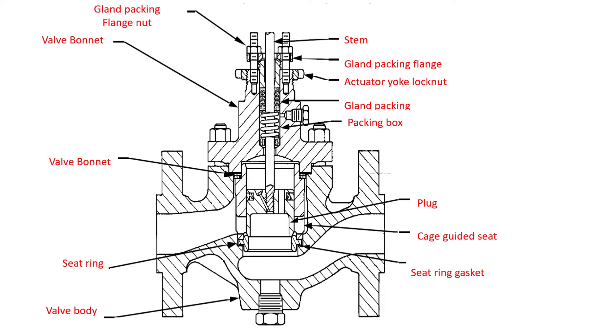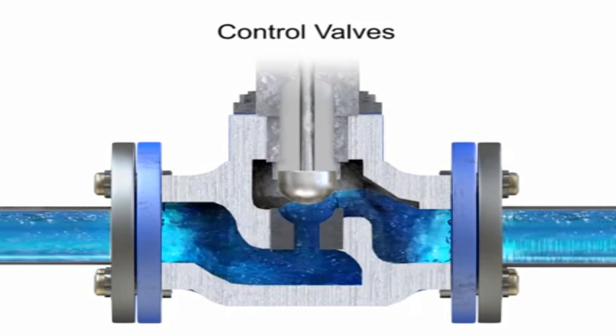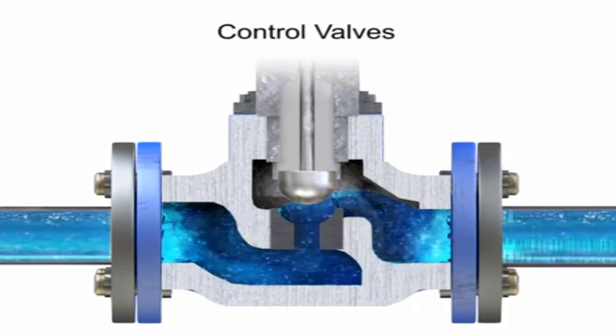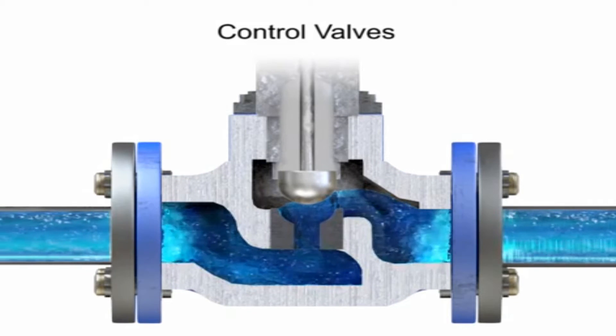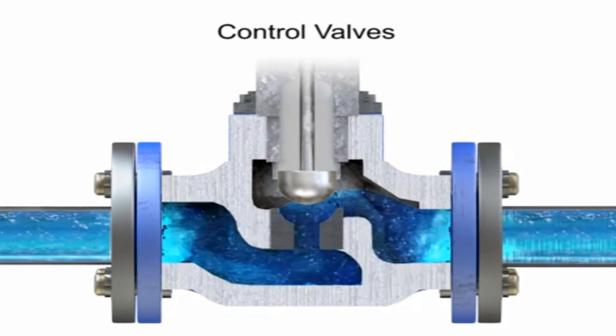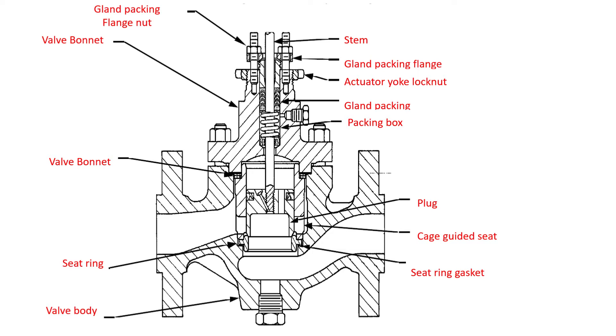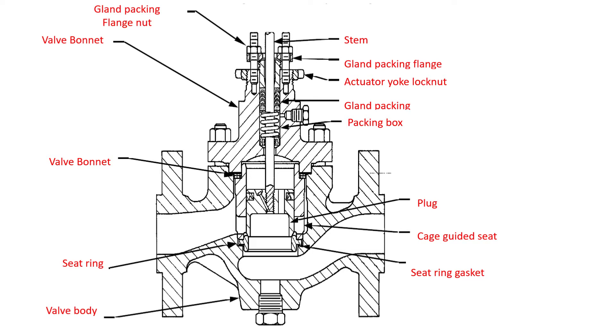Now, what is basically trim? The trim refers to the internal process-wetted components. The process fluid flows from inlet port to outlet port, and in between we have the plug stem system, the cage, and the seat ring. These components get wetted by the process fluid, so this area is called the trim.